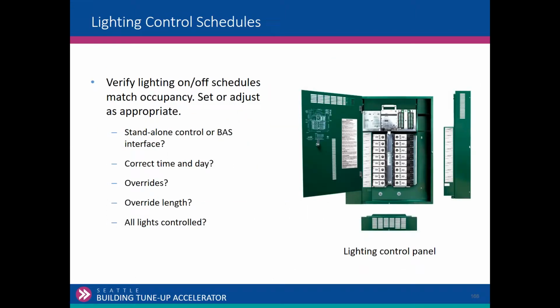Lighting control schedules. If you have a building that has a master control panel, is the date and time correct in the panel? Does the lighting schedule match occupancy? Are holidays programmed into that, or when the building is not occupied? What's the length of the override? If the override's 24 hours, 2 hours, what's appropriate? Are all the lights controlled? So if they do have central lighting control panels, again, it's just your best judgment. Is there an opportunity, low cost, no cost, through programming changes or scheduling that can reduce energy use?